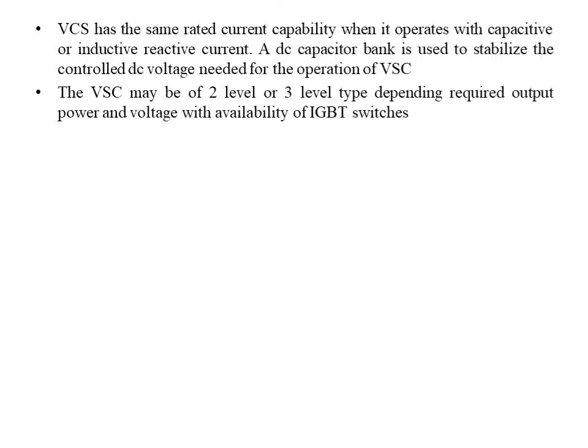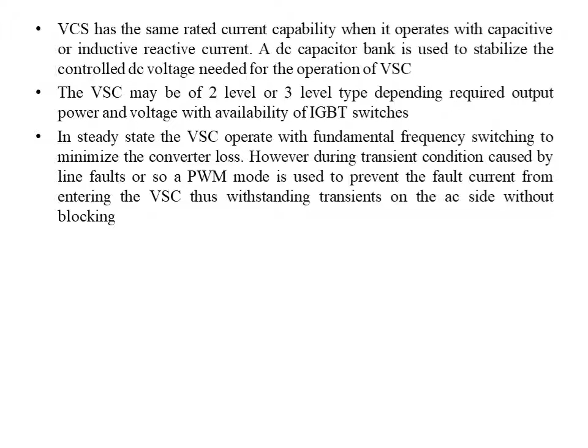In steady state, the voltage source converter operates with fundamental frequency switching to minimize the converter loss. However, during transient conditions caused by line faults, a PWM mode is also used to prevent the fault current from entering the voltage source converter, thus withstanding the transients on the AC side without blocking.